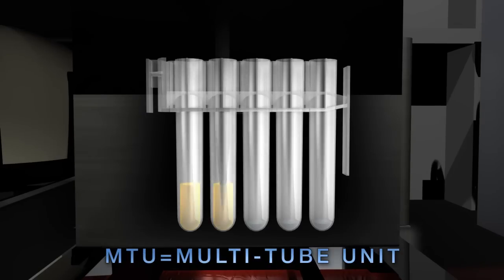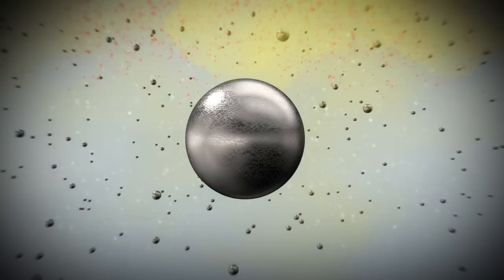The sample is aspirated and added to the multi-tube unit and mixed with the target capture reagent. The target capture reagent consists of small magnetic beads suspended in a solution.